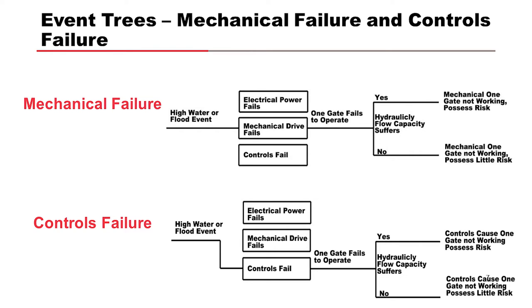If it's a project with two or three gates, the failure of one gate could be significant. So, same concept here, high water or flood event, mechanical drive fails, one gate fails to operate, yes or no, hydraulically flow capacity suffers. If it's yes, then the mechanical gate not working does induce some risk.